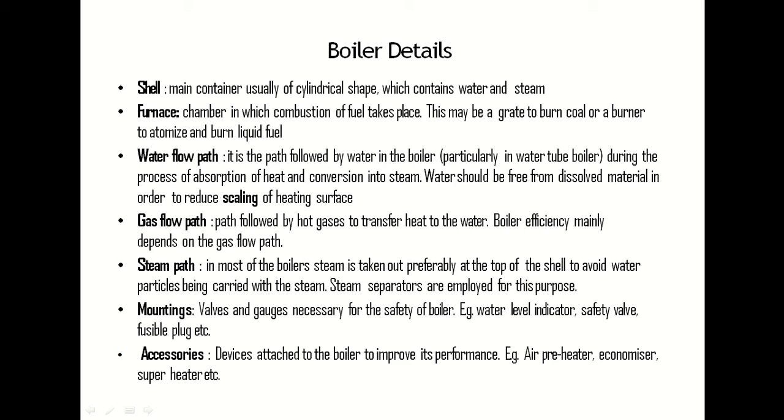Then next is the water flow path. It is the path followed by the water in the boiler, during the process of absorption of the heat and conversion into steam. This is generally in the water tube boilers. Water should be free from dissolved material in order to reduce scaling of heating surfaces. Obviously, if scaling increases, then the efficiency of the boiler goes on decreasing. The heat transfer rate will decrease, so to avoid that, the water should be free from dissolved material.